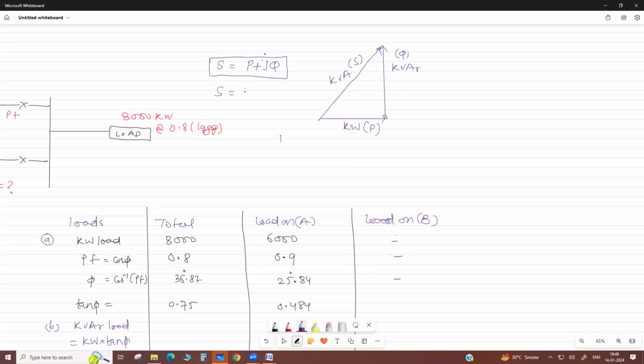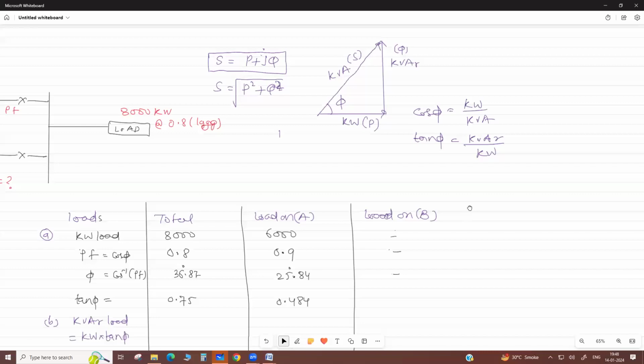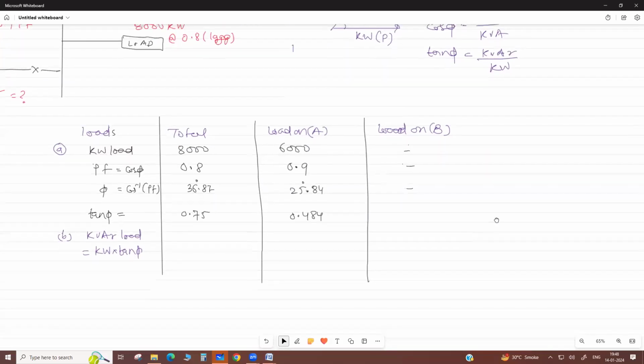So to find the magnitude, it is P square plus Q square, square root. Q square here. Clear? Now this is phi. The cos phi power factor is kilowatt by kVA. But if you write tan phi here, it means reactive power kVAR by kilowatt. This is what we use here - tan phi. kVAR equals kilowatt into tan phi.